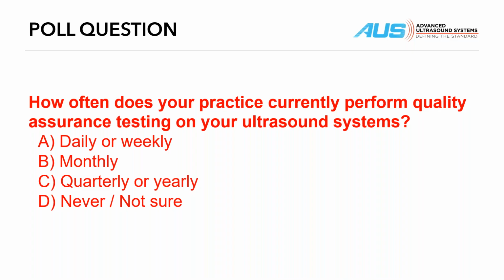Daily or weekly, I like, but really that becomes an operator function, with some people using the systems daily. It's not really FSEs or clinical engineers, biomeds, imaging engineers. We tend to do it more quarterly, semi-annually, or yearly. But in either case, it is important that you have a quality assurance program. So if you don't have one, it's something you should certainly set up and evaluate, because a lot of potential problems can occur, and we want to limit our liability and increase our ability to correctly diagnose patients.